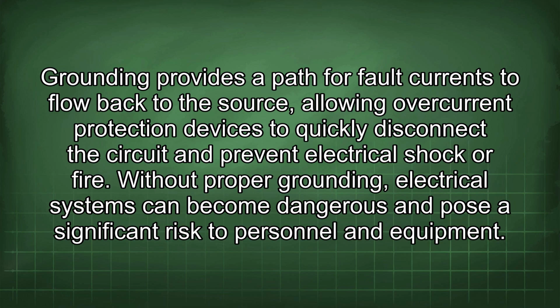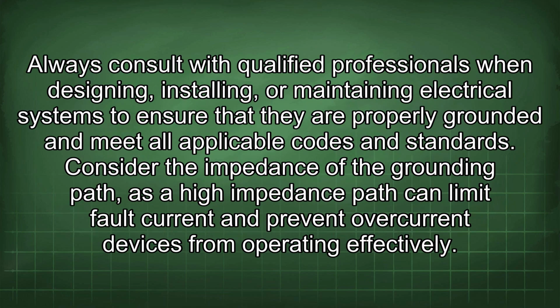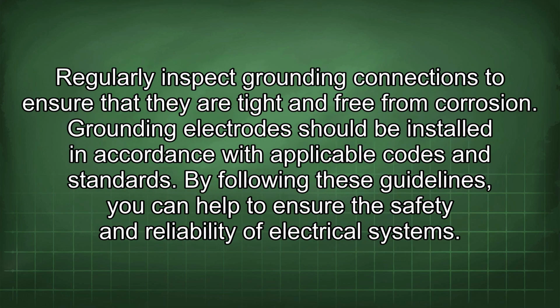Without proper grounding, electrical systems can become dangerous and pose a significant risk to personnel and equipment. Always consult with qualified professionals when designing, installing, or maintaining electrical systems to ensure that they are properly grounded and meet all applicable codes and standards. Consider the impedance of the grounding path, as a high impedance path can limit fault current and prevent overcurrent devices from operating effectively. Regularly inspect grounding connections to ensure that they are tight and free from corrosion.